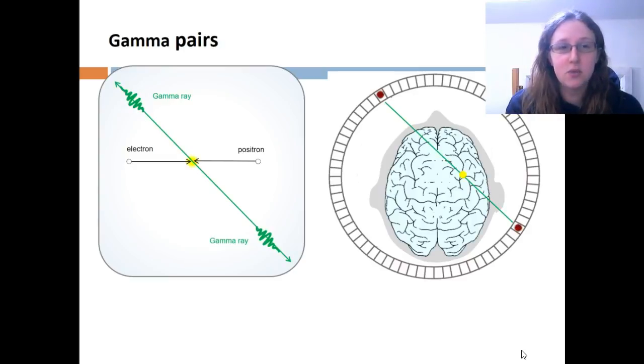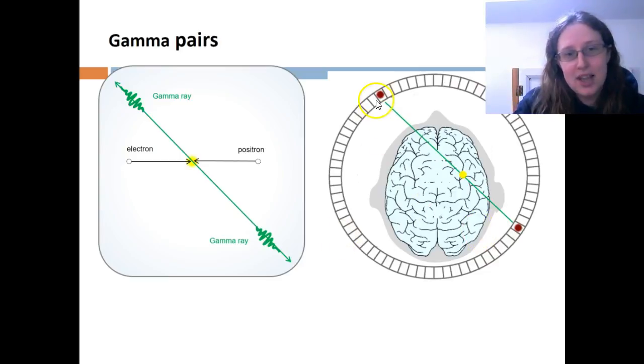The gamma rays are detected by a ring of detectors all around the patient. The two detections that arrive at the same time are used to figure out where the interaction came from. They look for two that are diametrically opposed. They will use the slight difference in the time they arrived to figure out exactly how far through the patient this occurred.